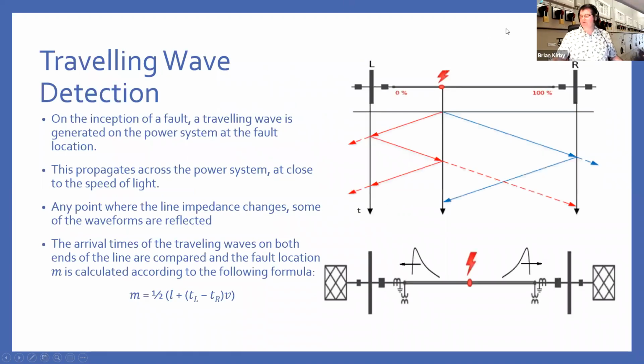So if we look at traveling wave detection, here we have a line from L to R, and we have a fault at some point on this line. At the inception of the fault, you will get a wave propagating, as shown here. You'll get a pulse, typically a very high frequency pulse generated at the very moment the fault occurs, and this will propagate across the line at close to the speed of light because of the high frequency.